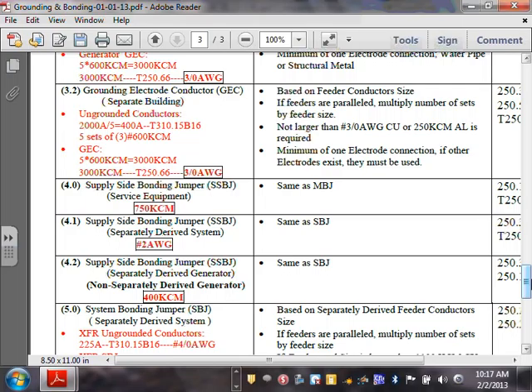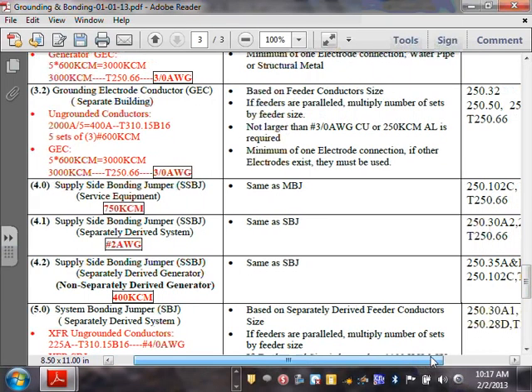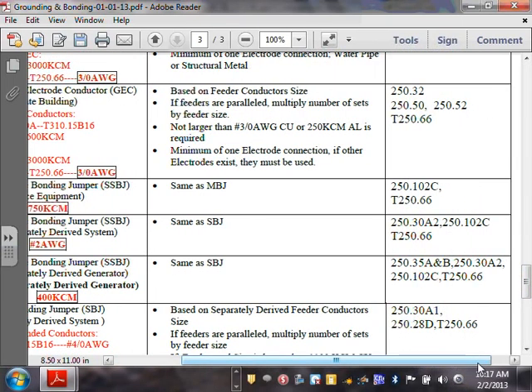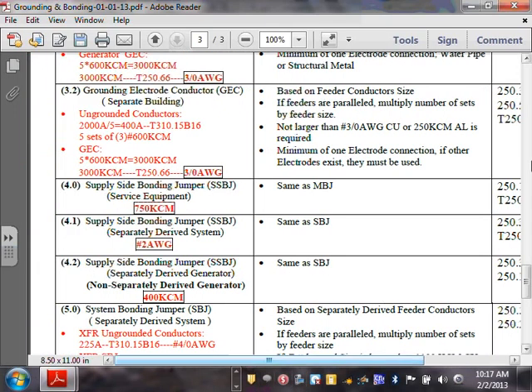Cool? So how do you size a supply side bonding jumper? Right here, same as main bonding jumper. Same as main bonding jumper. Okay, Chad, we haven't done the main bonding jumper. Let's go look, and if you don't believe your friend Chad, where do you go to check that? Here you go. Here's your reference in the NEC code book, right here. So let's go to the main bonding jumper. So that's supply side bonding jumper.